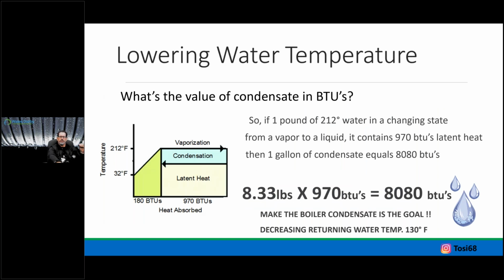With the process, and which and how, and to get to that, outdoor reset and collapsing, right? Wanting those flue products to be as cool as possible so that we can take advantage of what we call the latent heat. The loss that is typically leaving the building is fuel we paid for, right? How do we reclaim this? How do we achieve those high 90 percentile efficiencies on our equipment, right?